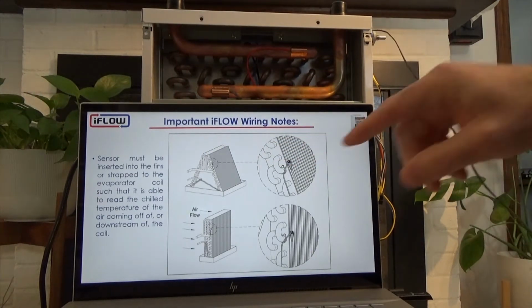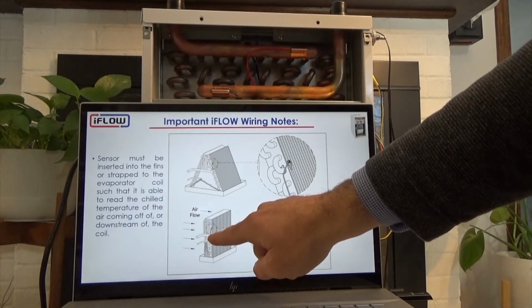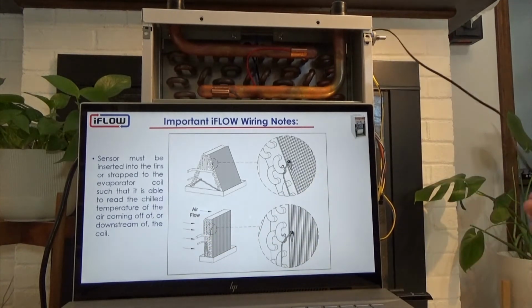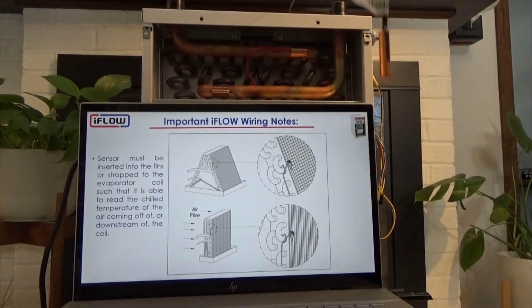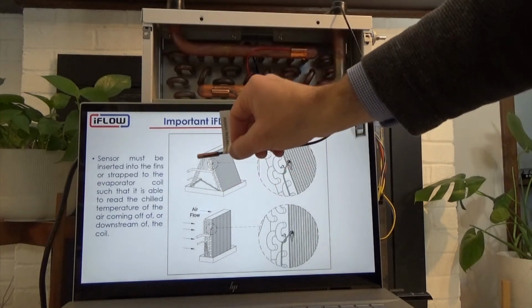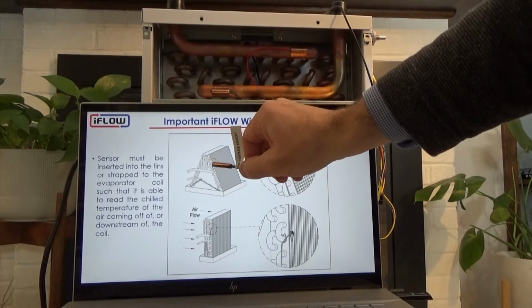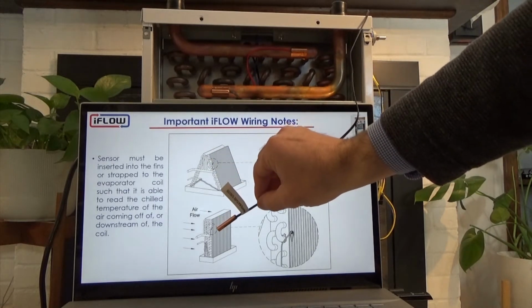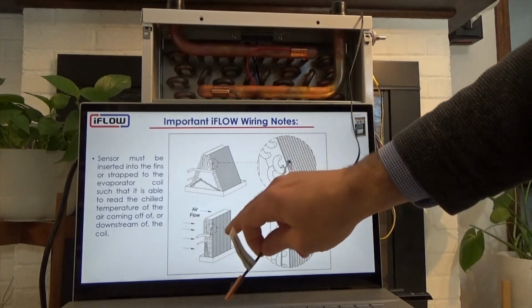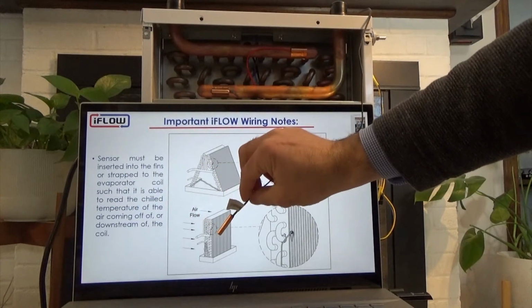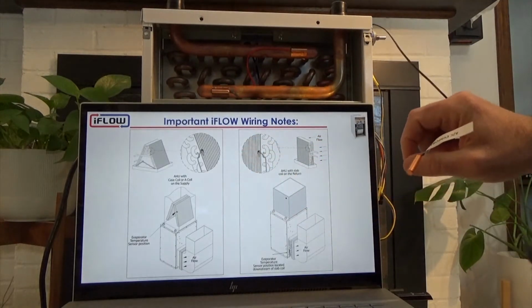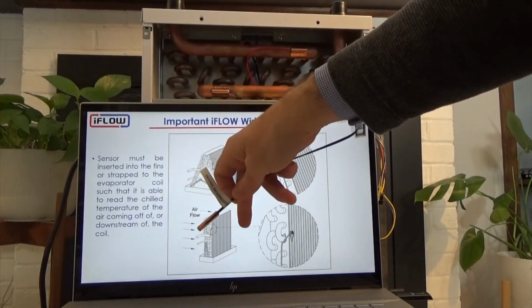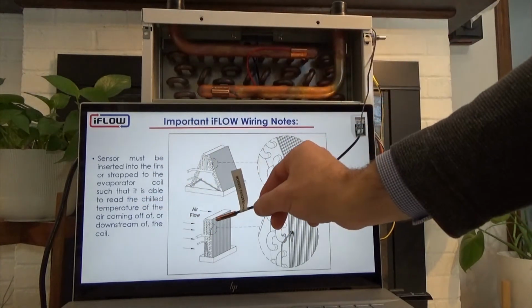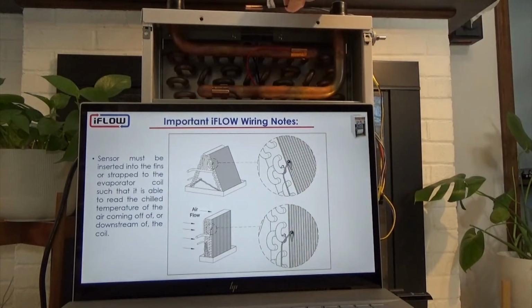When we are using a slab coil on the return duct, then we have to relocate the sensor from the top, because normally it's at the top of the unit, running with an AC coil on top of the unit, on the supply. But in this case, where we've got the return, it has to measure the temperature coming off the coil, so we have to look at the airflow. If the airflow was coming this way, this sensor would be downstream of that airflow, so it's properly sensing the air temperature coming off the coil. And again, that can fit into the fins of the slab coil as well.